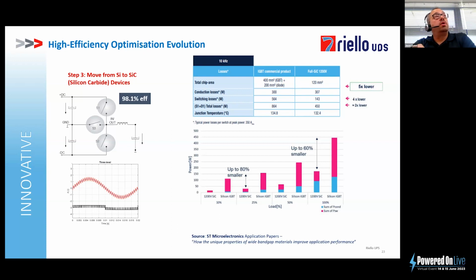So overall, using silicon carbide, we get around a 50% reduction in the heat generated by the device during operation. And the graph at the bottom there shows you the load levels across the components at 10, 25, 50, and 100% load. And as you can see, the silicon carbide devices constantly outperform the traditional IGBT device. So it's not as if the device just operates at a certain point or sweet spot. It will outperform the IGBT across the load ranges.